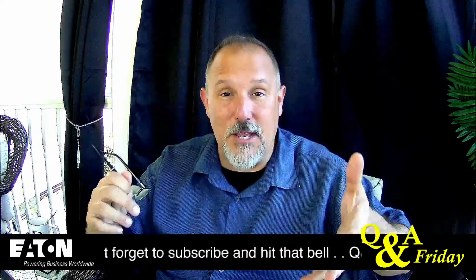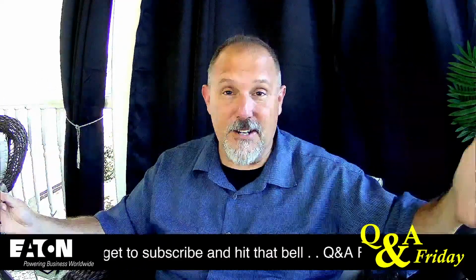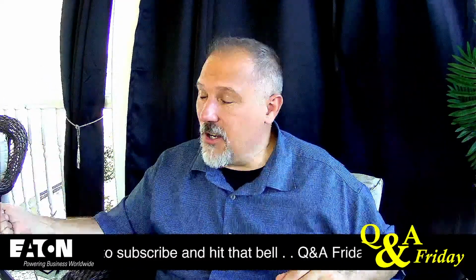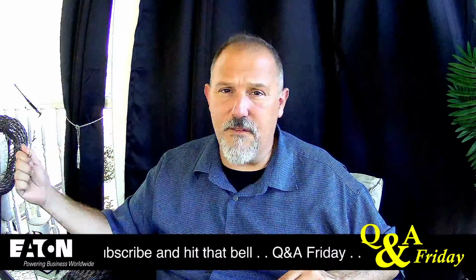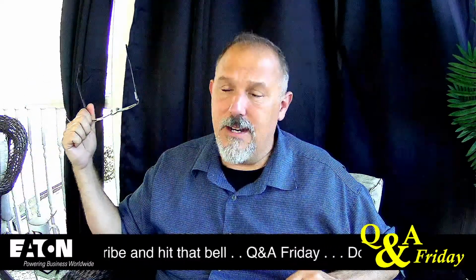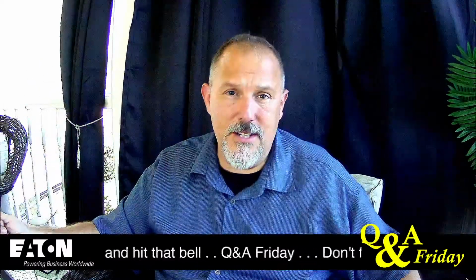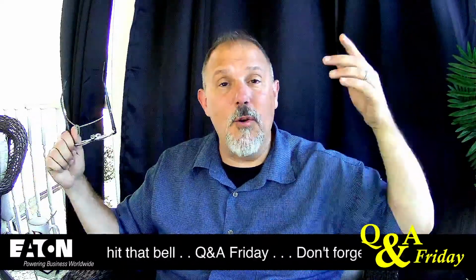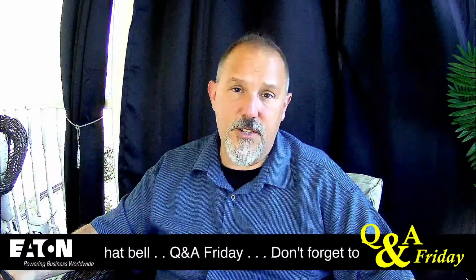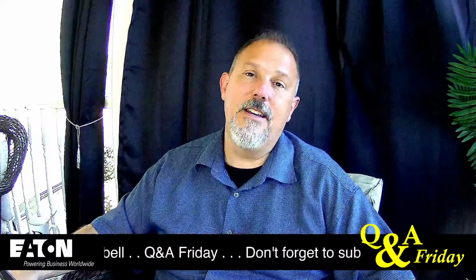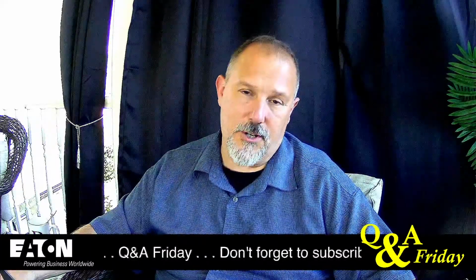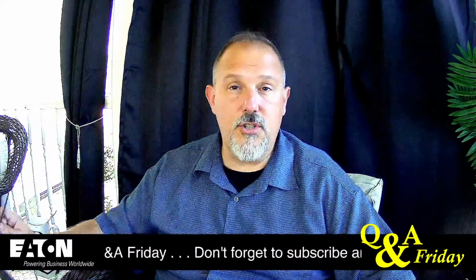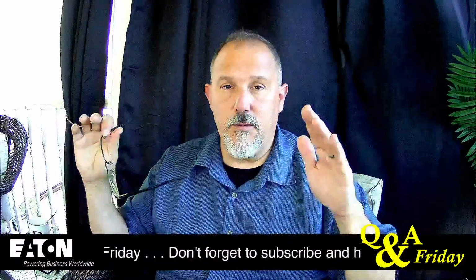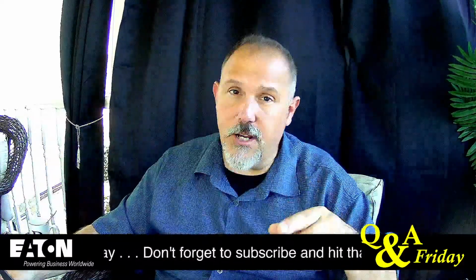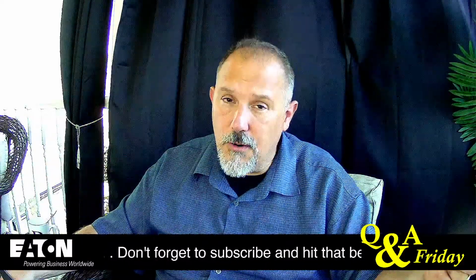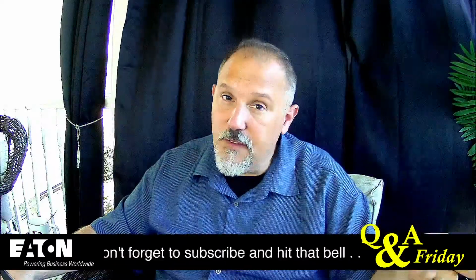So that's the other important thing: that is a service conductor. It connects that equipment, which happens to be a fire pump controller or a fire pump or maybe a fire pump disconnect, whatever it is, to the utility. And if you look at the definition of what a service conductor is, what a service is, in the National Electrical Code, that tells you you have to treat it that way. So just because you are dealing with fire pumps does not mean you can ignore Article 230, and you can't ignore Article 250.